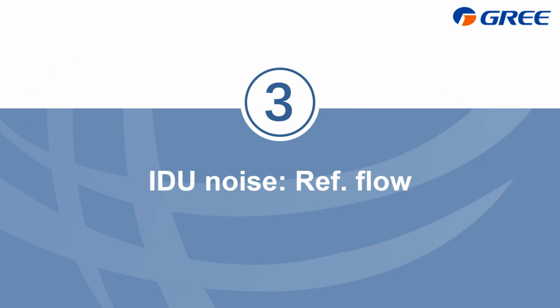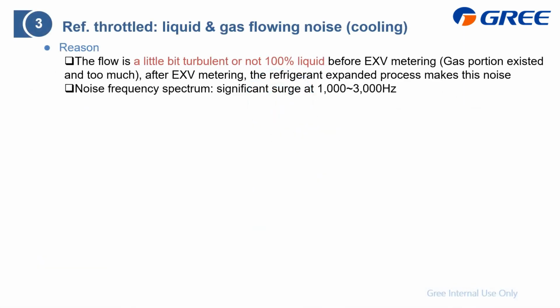Indoor unit noise from the refrigerant flow. Next, we will go to the refrigerant throttle or refrigerant metering noise. It is actually the liquid and gas refrigerant flow noise in cooling mode. First of all, I will show you the noise example just for your reference. Just like this.